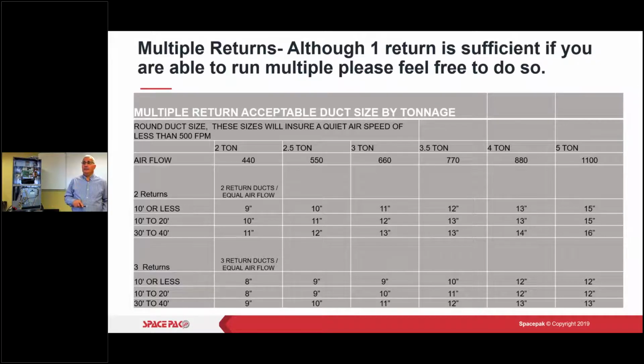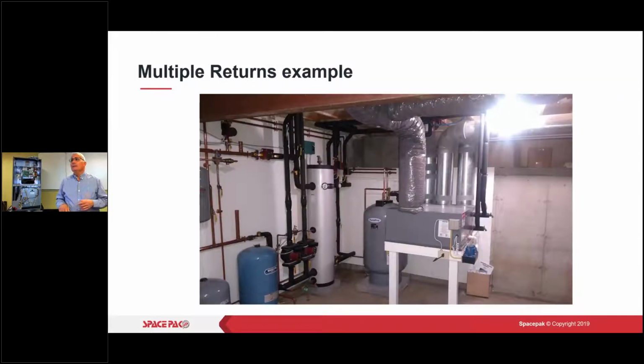If you take a look at this, gentlemen, you can take a screenshot if there's any information here that you want to save, and that'll save it to your computer. Here we're showing you, if you have 2 returns, the size of the ducting and the length of it based on tonnage. Here's a picture of multiple returns on a project. This happens to be a chiller job. That's a buffer tank right here, there's our horizontal air handler, and here's our multiple returns coming back.